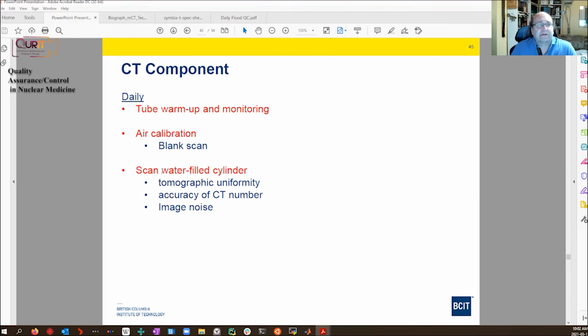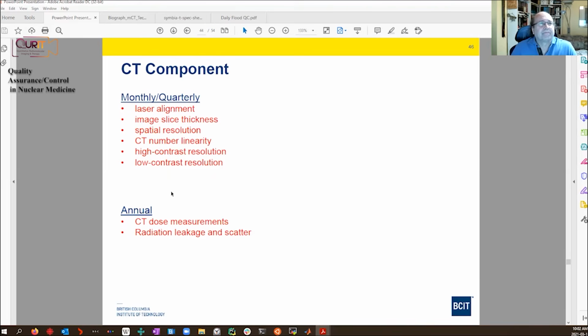Then there's the scanning of a simple water-filled cylinder. It's not radioactive, it's just a water-filled cylinder. The reconstructed image is assessed for uniformity to see whether that CT number is what it should be. It should be close to 0. And there's assessment of the noise. And then there are other routine tests that are done monthly or quarterly. I'm not going to go into them.